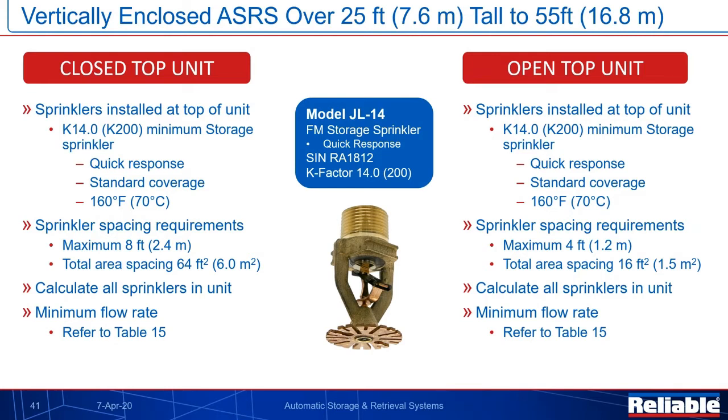We could probably end up looking at a standard answer for this of about 4 sprinklers per each one of these units. And when we look at the maximum dimensions, some of the maximum dimensions that are out there are in excess of 14 foot width and 14 foot depth. So we're definitely going to get up to the need for at least 4 sprinklers as a minimum in those types of units if we can space it correctly.